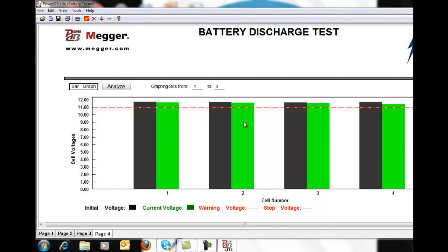If all of a sudden, for instance, cell number 2 was rapidly decaying, this gives me the opportunity to go back, pause my test, take corrective action, for instance, jumper out cell number 2, and then continue my test. I do not want that cell to decay or go to cutoff prematurely, because there is a risk that that cell may go into reversal.